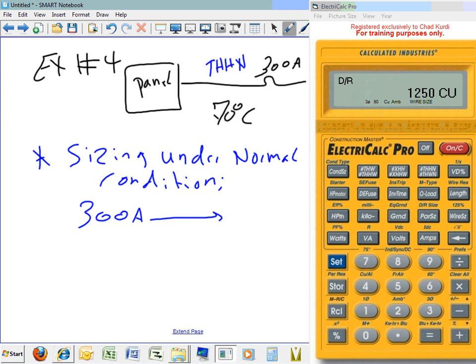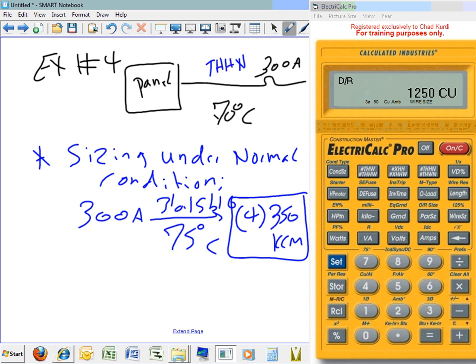amp, take it to 310.15(B)(16), under which column and why? 75C. Would that be 4 or 350? More than 4, so 4 conductors, 350 kcmil. Let me just see if my calculator comes up with the same size, would you?